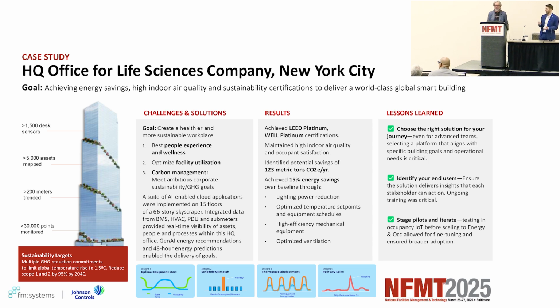The last one I'll point out: meters can be expensive. So we looked at every single fan-powered box within a space and created virtual profiles for those meters to calculate their electrical and thermal loads. Now we can see the energy profile for every box in the conference rooms, every space. When we plot them against each other and do peer analysis, we see a common trend, and then all of a sudden a handful of boxes way up there, using four times the energy they're supposed to.